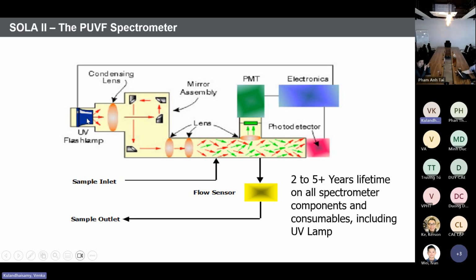The UV lamp needs to give a constant wavelength of light. Whenever the lamp deteriorates, the light energy will go down, right? That will be detected by the photosensor. Then the photosensor gives feedback to the electronic circuit. Then the electronic circuit will inject more voltage to the UV lamp to maintain the wavelength. So this is a feedback circuit. That's why you are able to get a constant wavelength, constant density UV light from the UV lamp source.